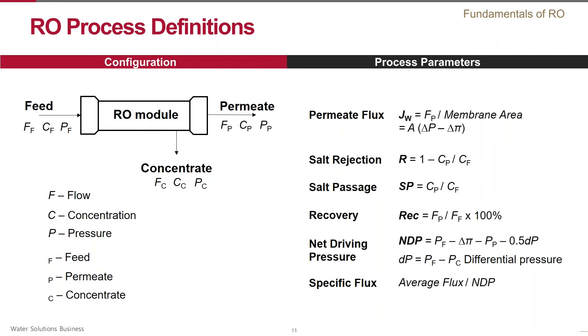Another important parameter is recovery — it describes what volume percentage of feed water is recovered as permeate. We already know what NDP is: net driving pressure, which is the pressure available to drive the feed water through the membrane minus the osmotic pressure and the permeate back pressure. We also add losses associated with flow along the membrane — dp, the difference between the feed and concentrate pressure, called differential pressure. Finally, specific flux characterizes the resistance of the membrane to water flow and is calculated by dividing the average flux by NDP — it is analogous to the water transport coefficient A in the RO transport equation.